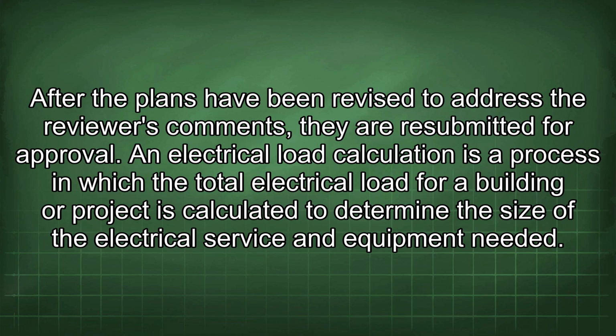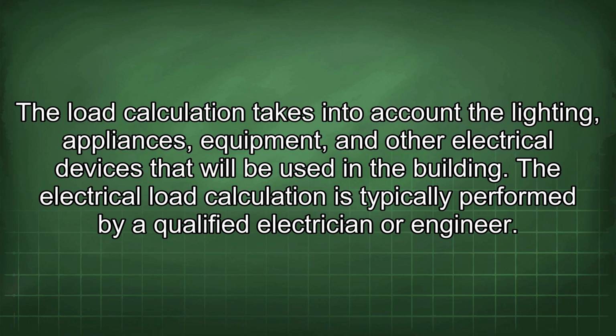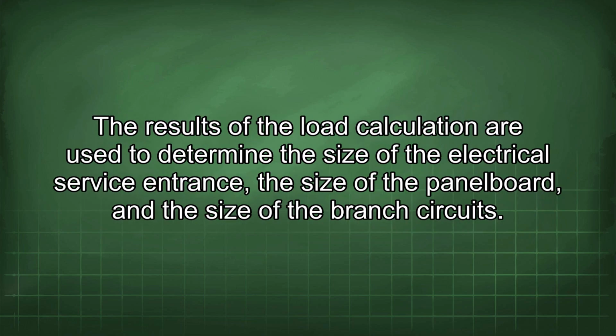An electrical load calculation is a process in which the total electrical load for a building or project is calculated to determine the size of the electrical service and equipment needed. The load calculation takes into account the lighting, appliances, equipment, and other electrical devices that will be used in the building. The electrical load calculation is typically performed by a qualified electrician or engineer. The results of the load calculation are used to determine the size of the electrical service entrance, the size of the panel board, and the size of the branch circuits.